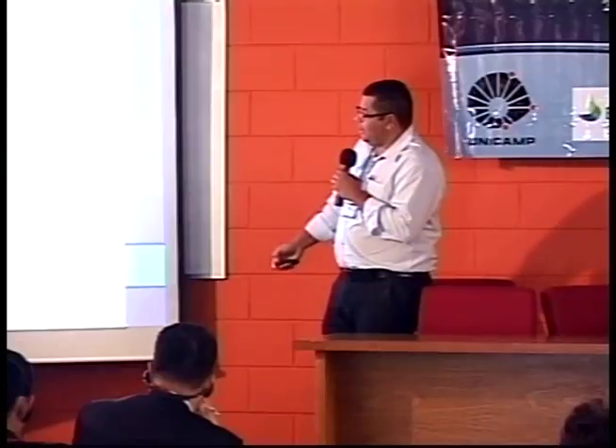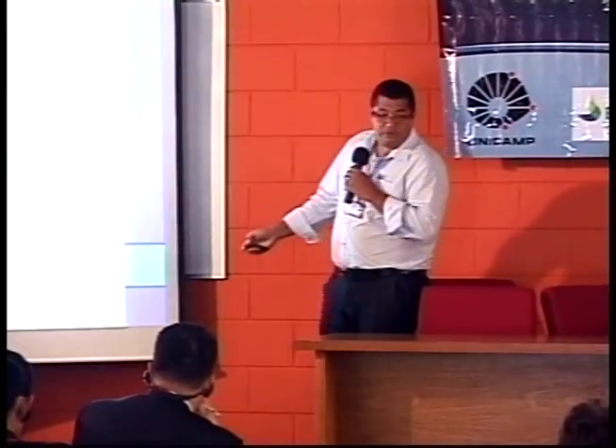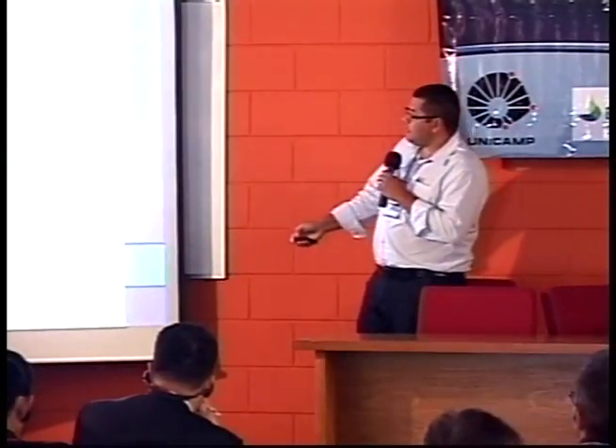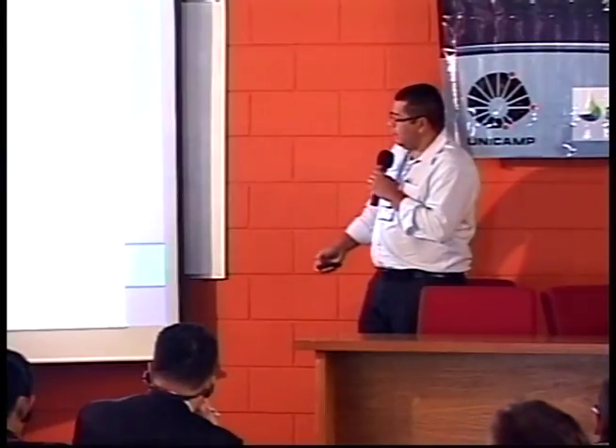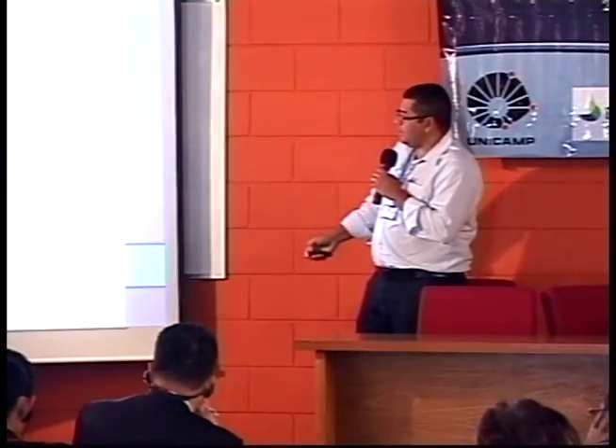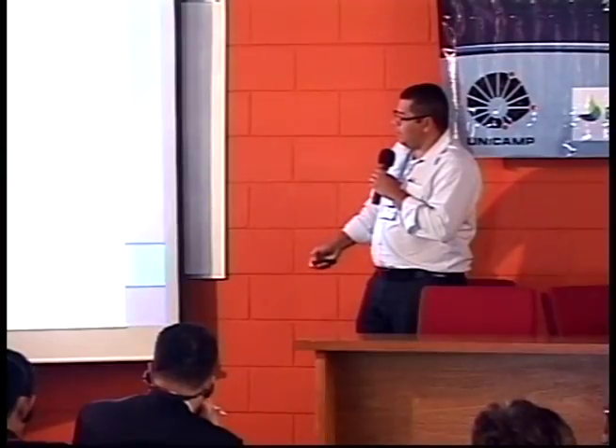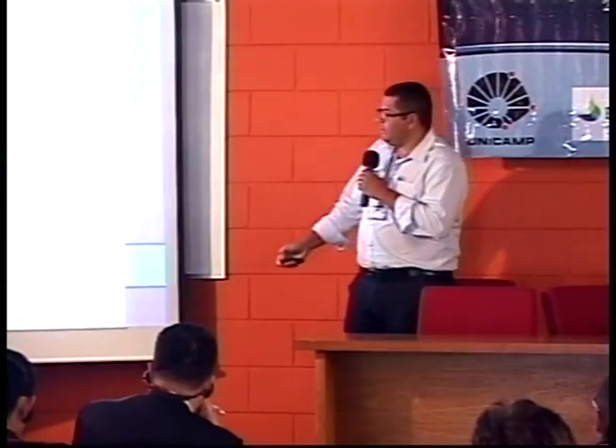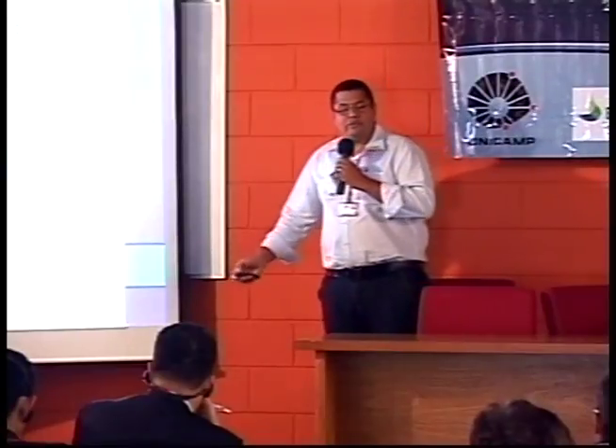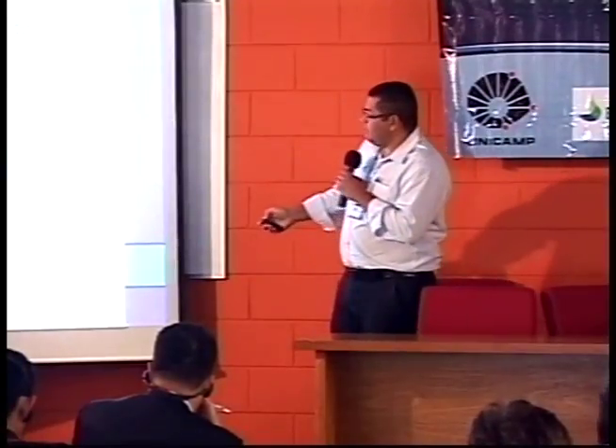So here we would calculate this ideal tap for all the scenarios, considering 3 lines of 800 kV and 2 lines of 800 kV. Here, 2 lines of 800 kV, we're going to work with a higher voltage level. In 3 lines, we're going to have to drop the voltage level even more. So what do we do? We find the ideal tap. We create 5 values below and 6 above this ideal tap. So we have 12 tap positions. It will be around 10% of variation around the ideal tap.